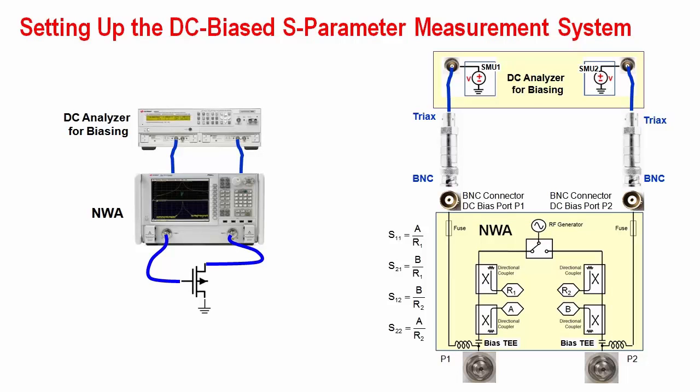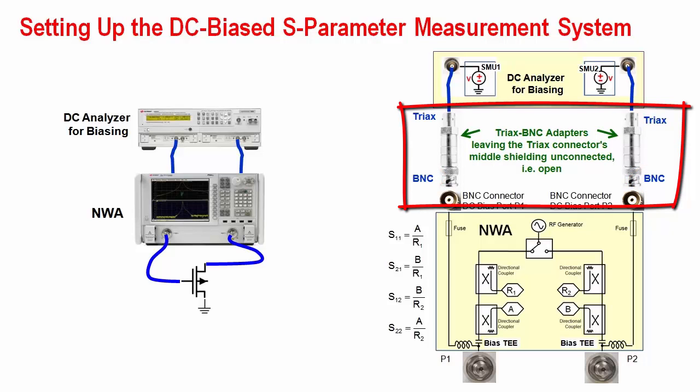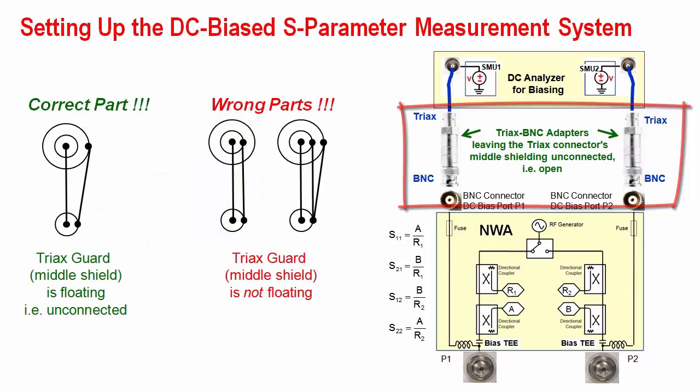But there is a problem. While the DC analyzer has triax connectors, the network analyzer has BNC. Therefore, we have to apply adapters. The challenge is to use an adapter which leaves the middle shielding of the triax cables absolutely unconnected. The correct adapter type shown is here on the left. Make sure to only use this one.